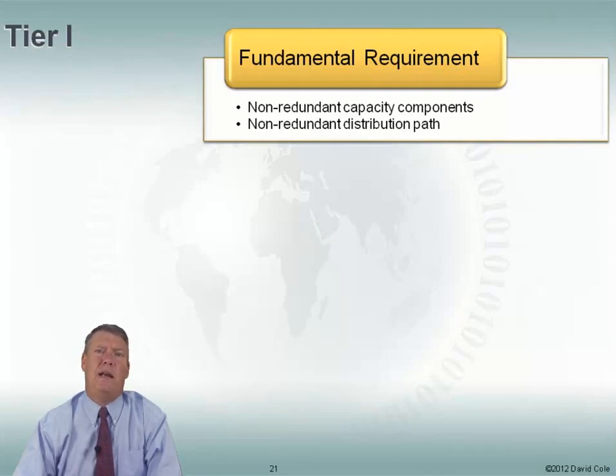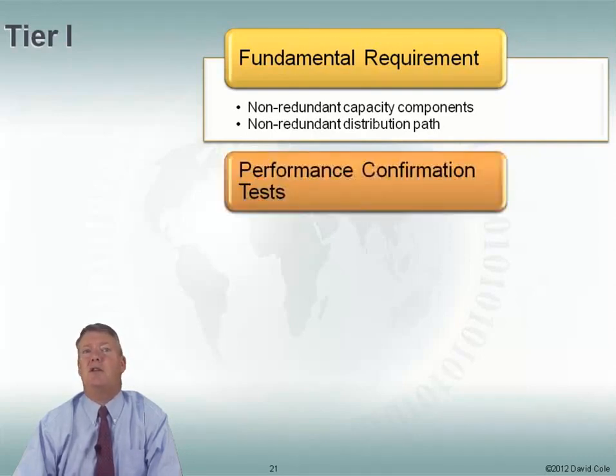For example, maybe I have enough cooling in my data center, a computer room air conditioner to cool it, but what happens if that breaks? I don't have a spare. Second, there's a non-redundant distribution path, which is all about electricity, how power gets to my equipment. On a Tier 1, both of these are non-redundant, meaning no backups, no spares. Let's look at what this means for performance.